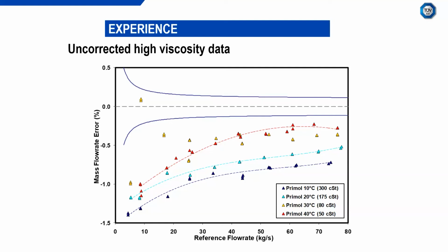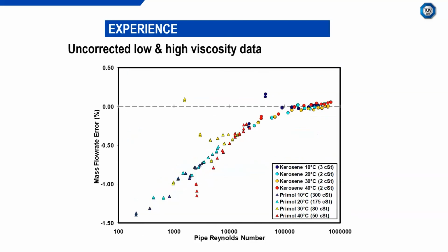Now what we've done in the next slide is look at these results plotted against Reynolds number. These results are outside specification, all apart from those two yellow points, just by chance, caused by zero effects. It actually made it within specification, but 99% of that data is out of spec. Now if we plot all the data, that's both the kerosene and the Primol data, against Reynolds number, you can see that there's a definite Reynolds number effect, and it's linear. There are zero effects as well, so that's why you see some of those deviations, the yellow and the red points, and even the blue up at the top there. That's more than likely zero effects.